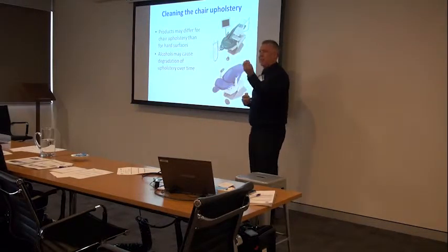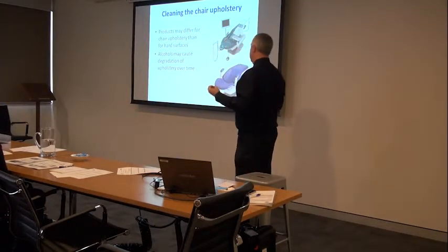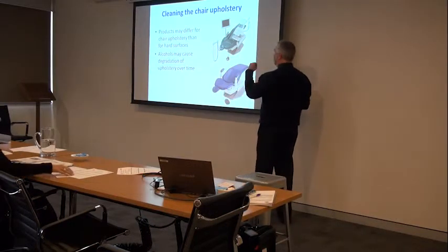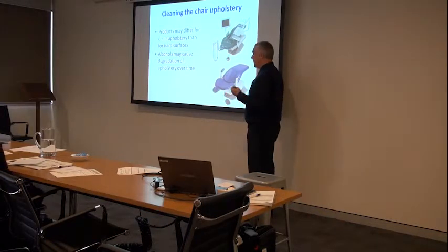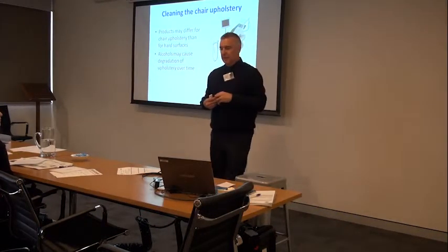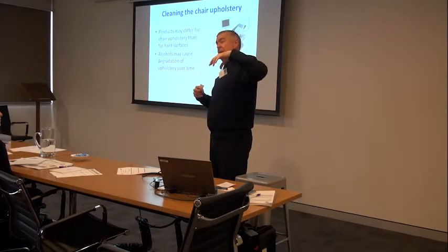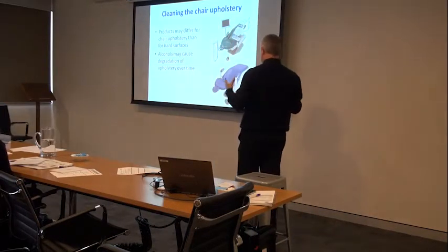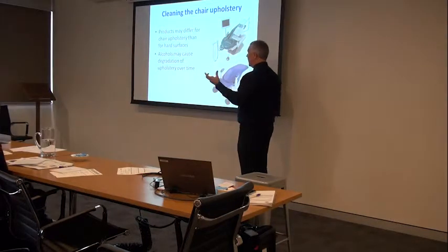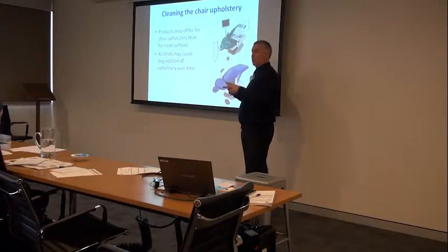If you have something that's heavily fragranced, some fragrances also attack components of dental chairs. One particular fragrance is notorious for attacking plastic polymer, and that is one of the fragrances from tea tree oil. So if you have something that's heavily flavoured with tea tree oil and you use that on plastic, you'll find that plastic will start to go a bit yellow over time. That's no accident. You're actually breaking up the polymer structure of the plastic because of the action of that particular phenolic agent.